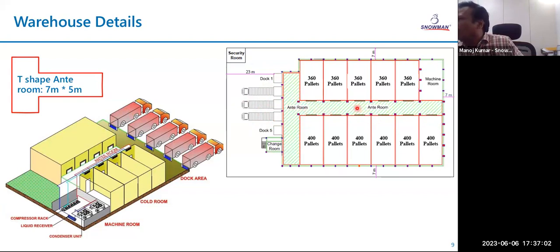The anteroom is where we maintain plus 10 to plus 15 degrees. It is to avoid thermal differences, especially when the chamber is frozen at minus 18 degrees and the door is open. If the outside is ambient, there will be a drastic increase in the temperature. To avoid that, we have this anteroom at plus 10 degrees, so that the effect will be much lesser. This anteroom will also have a door and partitions, so that the temperature is maintained.